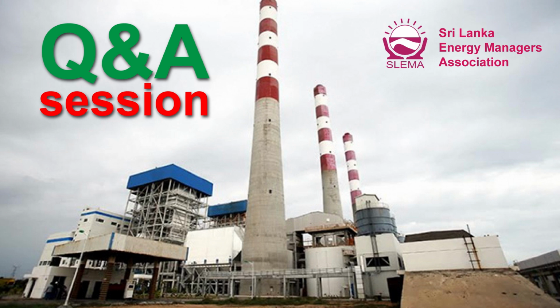Now, take these equipment, let's say a 5 megawatt pump. It's a big pump. When you start a pump, even with, let's say, a 30 megawatt diesel generator, when you simply close it, it will draw a very large inrush current. The starting current will be very high. Now, when that happens, you have to propose some startup mechanism as well, starting methods as well.